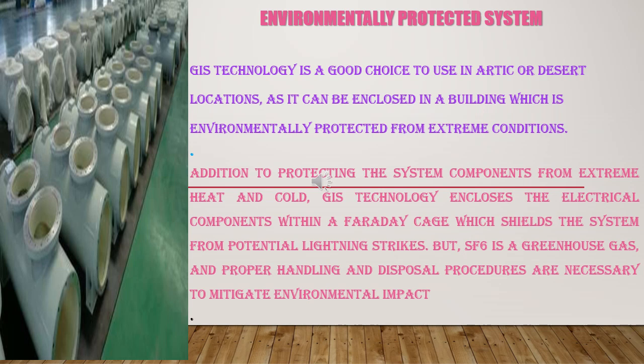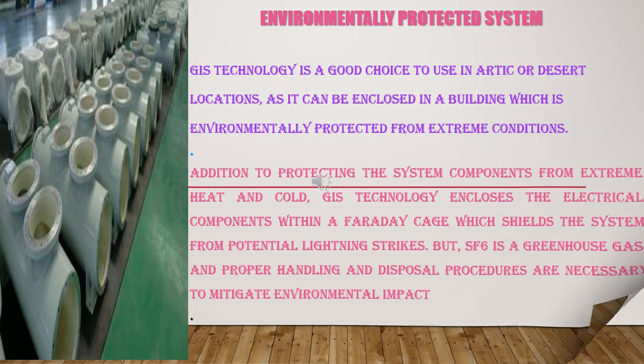Environmentally protected system. GIS technology is a good choice to use in Arctic or desert locations, as it can be enclosed in a building which is environmentally protected from extreme conditions. In addition to protecting the system components from extreme heat and cold, the technology encloses the electrical components within a Faraday cage which shields the system from potential lightning strikes. But SF6 is a greenhouse gas, and proper handling and disposal procedures are necessary to mitigate environmental impact.